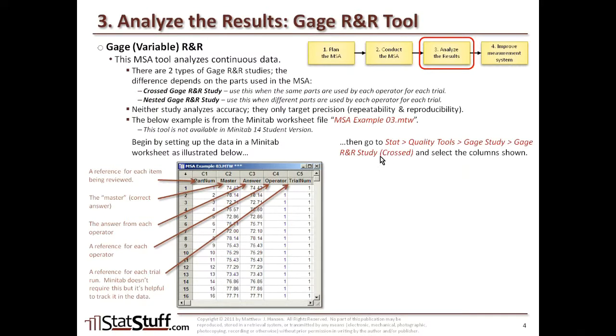When you want to load the data and start to run this test in Minitab, go to the Stat menu, then Quality Tools, then Gauge Study. In this example, use the Gauge R&R Study Crossed, since we're using the same parts for each operator. The output results look very similar between crossed and nested, but it matters that you select the right test depending on how you set up your parts and conducted the MSA in step two.